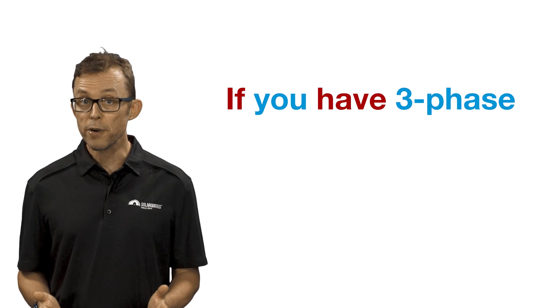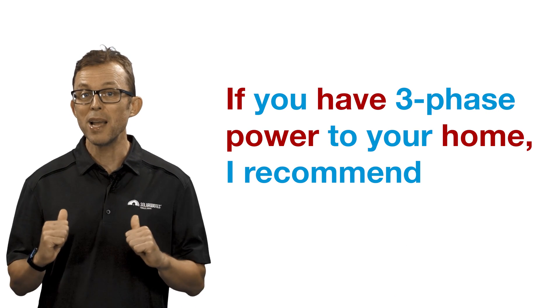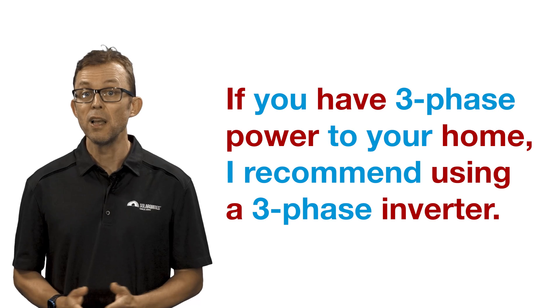Now, a quick note for houses that have three-phase power. If you have three-phase power to your home, I recommend using a three-phase inverter. You can use a single-phase inverter on a three-phase home, but you are more likely to have what's known as over-voltage issues if you push all your solar exports down a single wire instead of three. So I'm a big fan of three-phase inverters for three-phase homes.